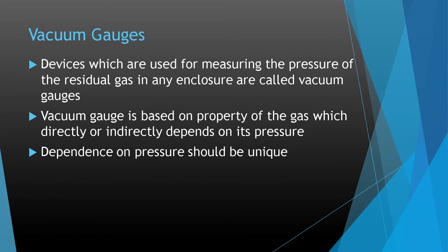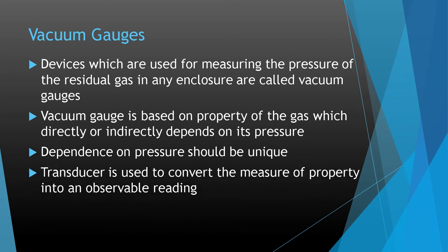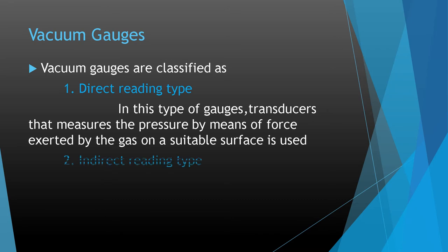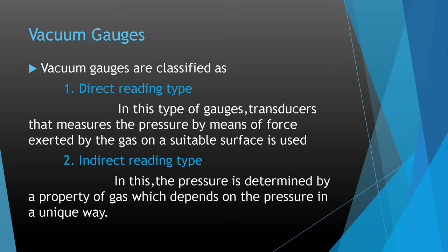The dependence on pressure should be unique. A transducer is used to convert the measured property into an observable. Vacuum gauges are classified as direct reading type and indirect reading type. In the direct reading type, the transducer measures the pressure by means of the force exerted by the gas on a suitable surface. In the indirect reading type, the pressure is determined by a property of the gas which depends on the pressure in a unique way.